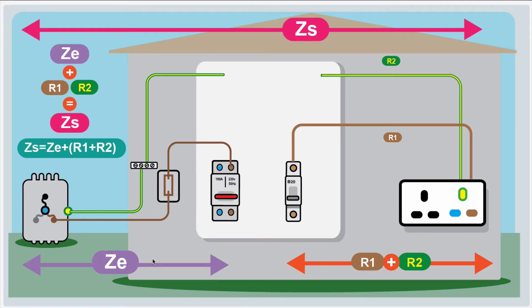It's important to understand the relationship of ZE to the rest of the installation. ZE is the external part. We also have the internal part of the property — your fuse board and all your current-using equipment — and this is measured with R1 plus R2. R1 is your line conductor going to your protective device into the plug socket, and R2 is your CPC going back to the fuse board. So ZE is external, R1 plus R2 is internal, and when you combine them both you get ZS — your earth fault loop impedance for the entire installation. The formula is: ZS = ZE + R1 + R2.